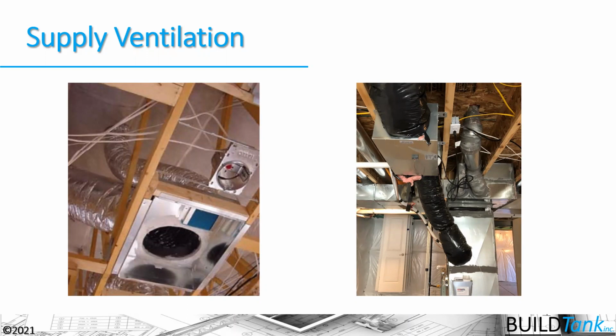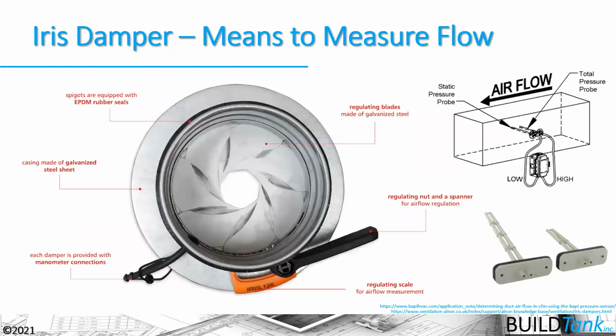The one on the right is one of those inline fans in the duct running from the outside to the return side of the furnace. I have a little bit more control and predictability. Where I'm going to get more control and predictability is if I use something like this iris damper, where I can change the orifice size here and measure the flow rate across that iris opening, and I can determine exactly how much air is moved through the system.